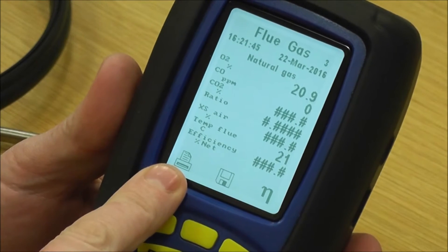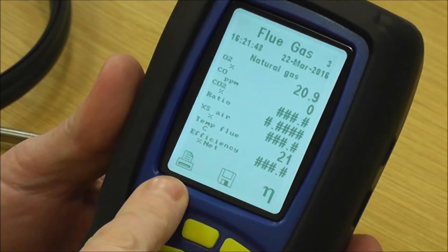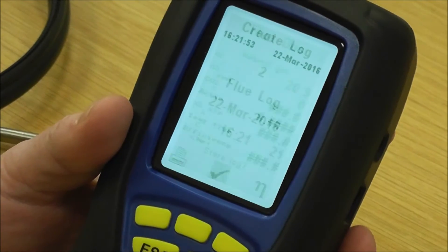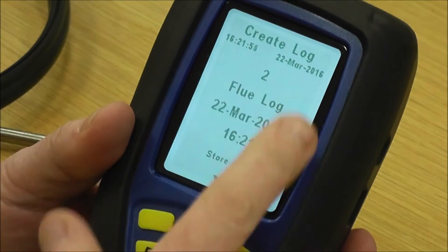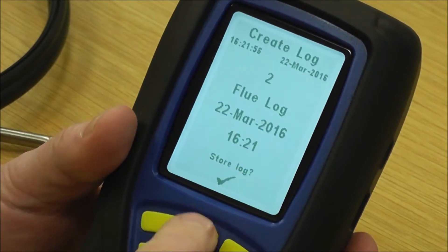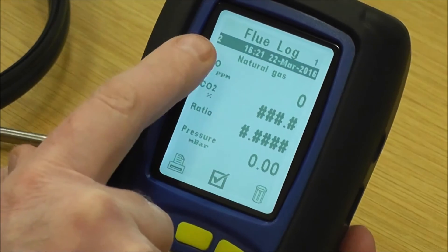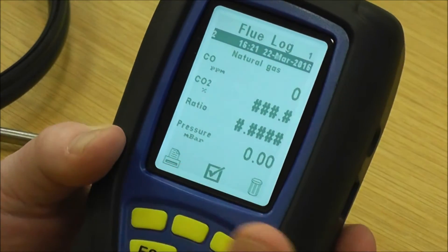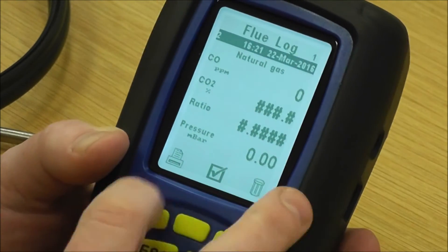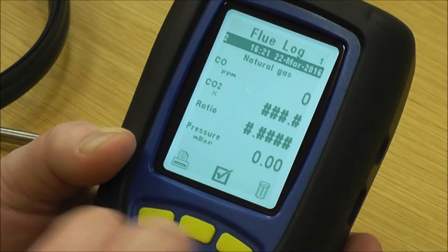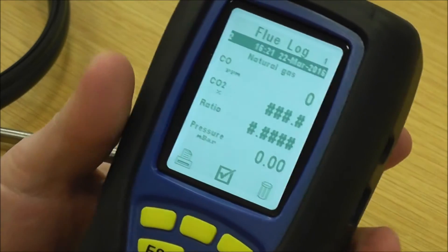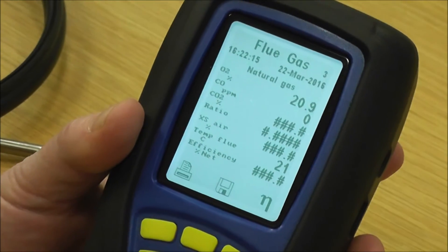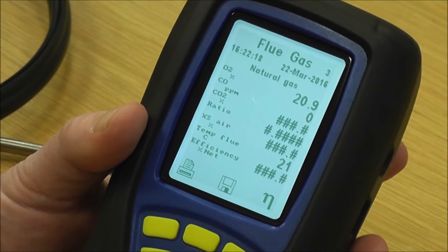This button is for print, and this one is set for the printer — if you've got a Bluetooth version, there'd be a Bluetooth sign there. The disk is the save key. If I press save, it shows what log it is — it's a flue log — and the date and time. You say yes and it freezes the readings on the screen. You can see log two up there, and the band at the top means it's frozen. Now I can pull across a printer and print. While the readings are frozen, if I press escape, it puts me straight back to live readings and I'm ready to do a new test.